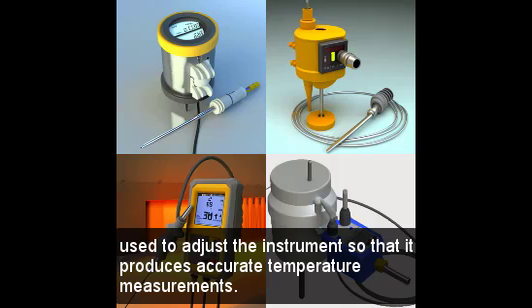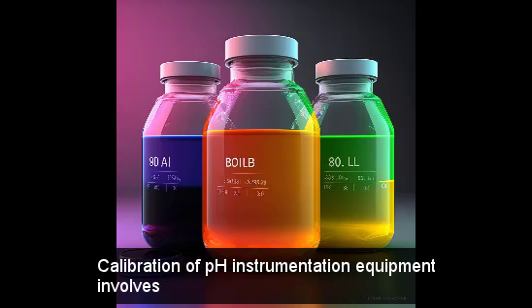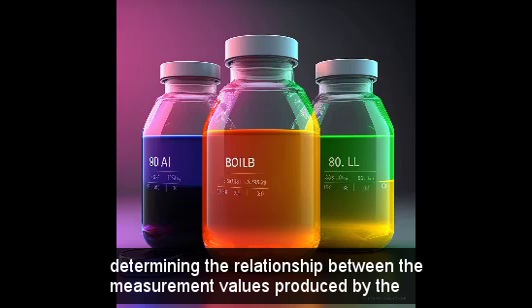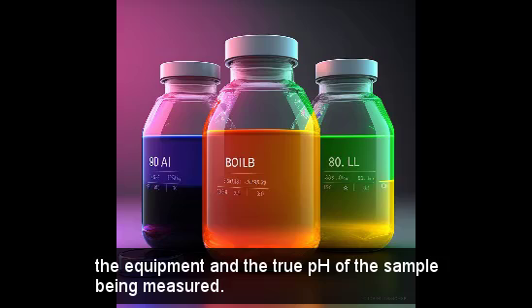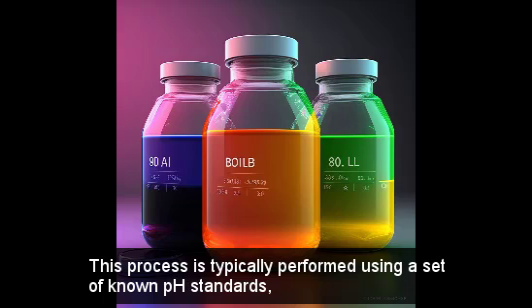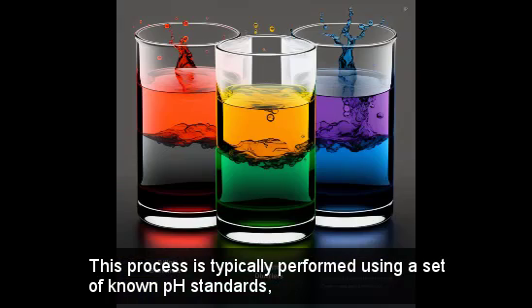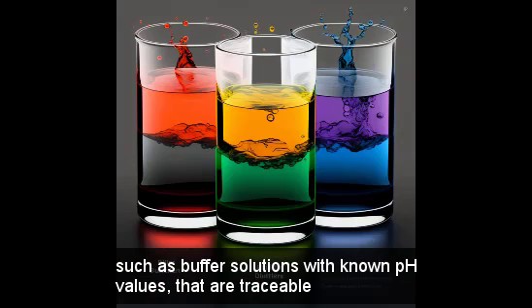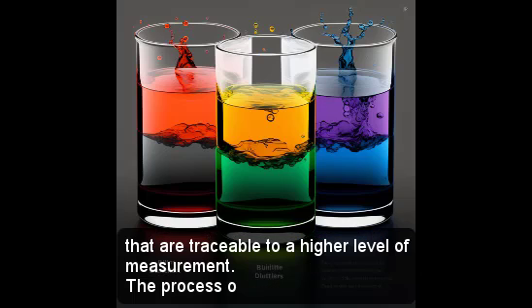accurate temperature measurements. Calibration of pH instrumentation equipment involves determining the relationship between the measurement values produced by the equipment and the true pH of the sample being measured. This process is typically performed using a set of known pH standards, such as buffer solutions with known pH values, that are traceable to a higher level of measurement.